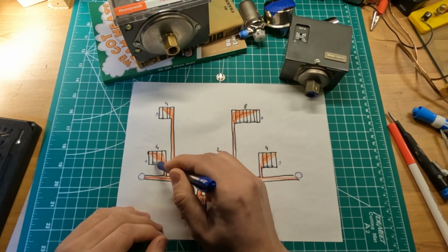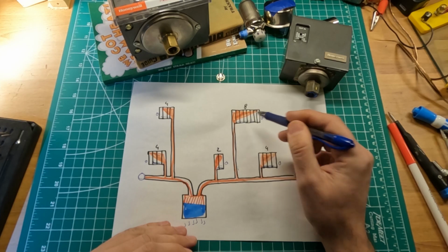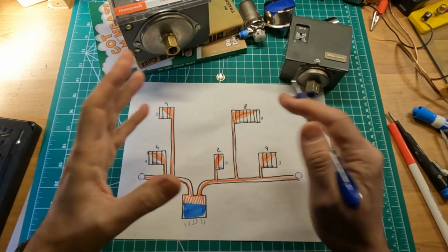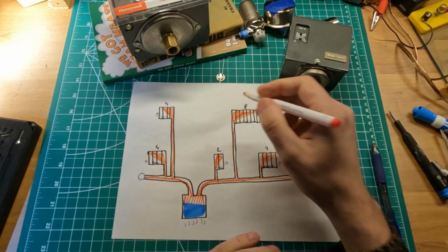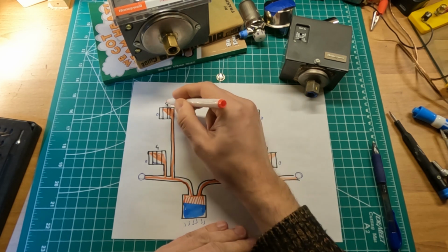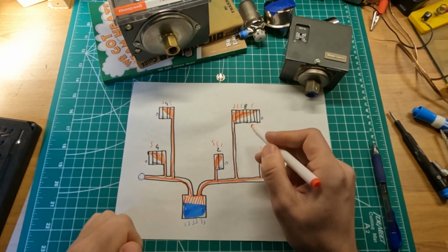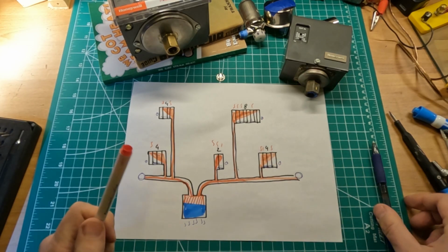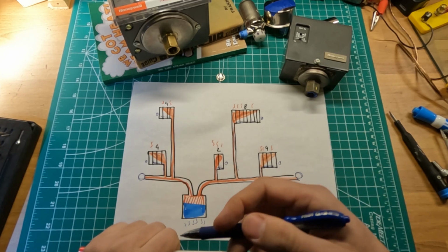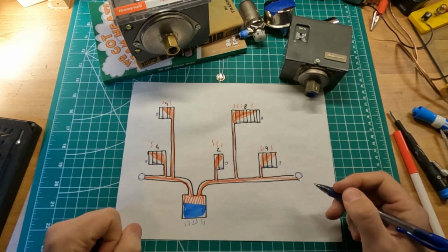And that condensate, besides partially warming up the radiator, also cools it off, because the purpose is not to have a hot radiator, but for the radiator to give out its heat to the surrounding space. And as it's doing that, the vents open up again, waiting for more steam to enter those radiators, and the cycle keeps repeating over and over.